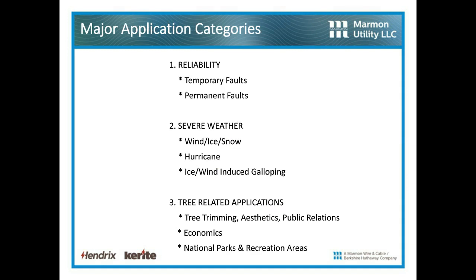Let's take a look at the major application categories. Obviously, the biggest one for spacer cable is reliability. We are going to completely eliminate temporary faults, no more. Permanent faults, it depends. We're going to probably mostly eliminate permanent faults, but it always depends on what hits the pole. Severe weather, we're great in wind, ice, and snow. Hurricanes, we're not going to have any galloping anymore, for ice or wind-induced galloping, because essentially we have a vibration damper every 30 feet, which is the spacer.